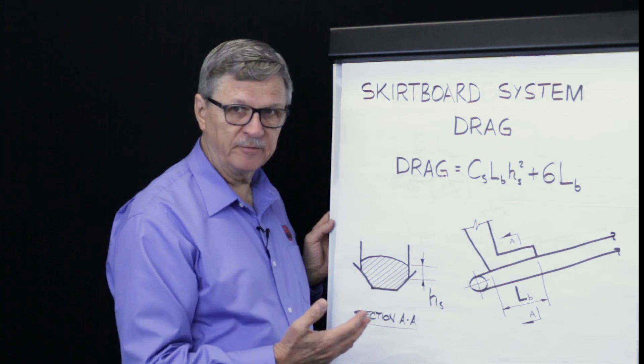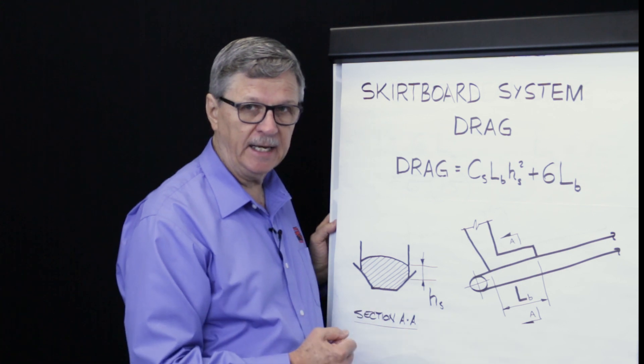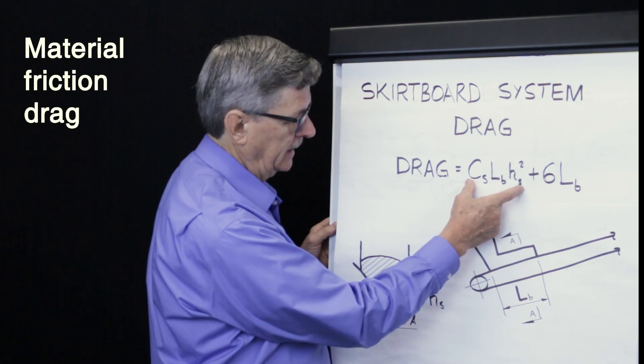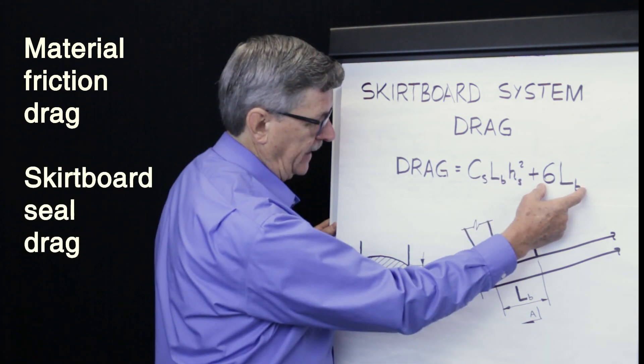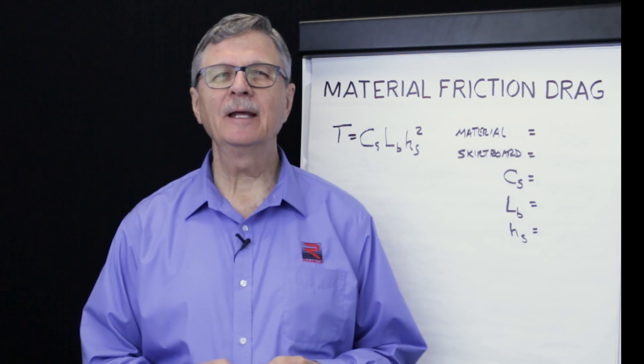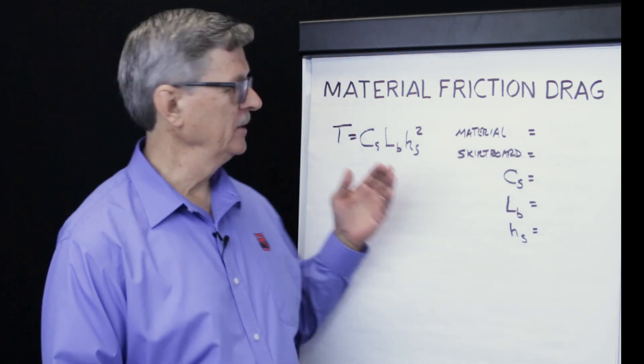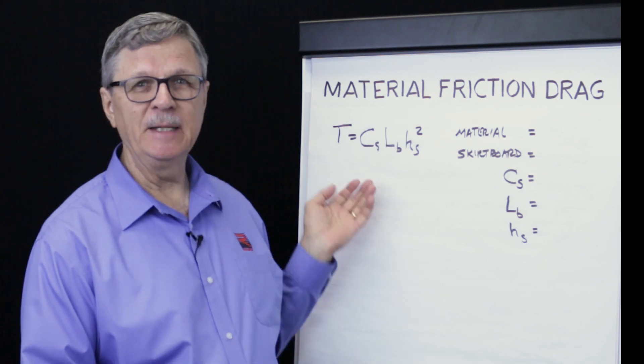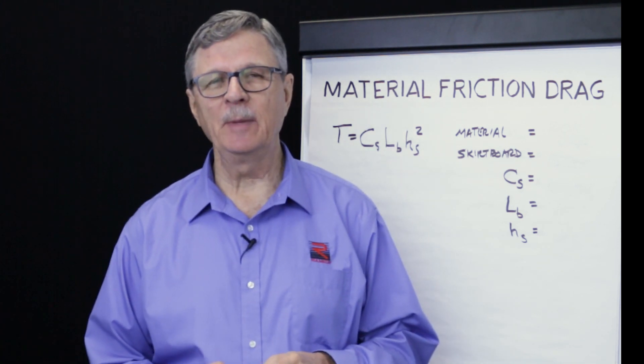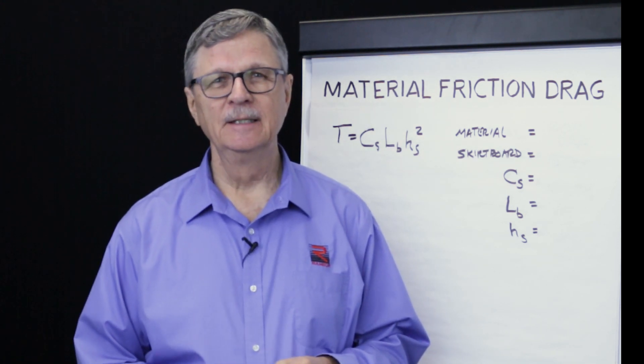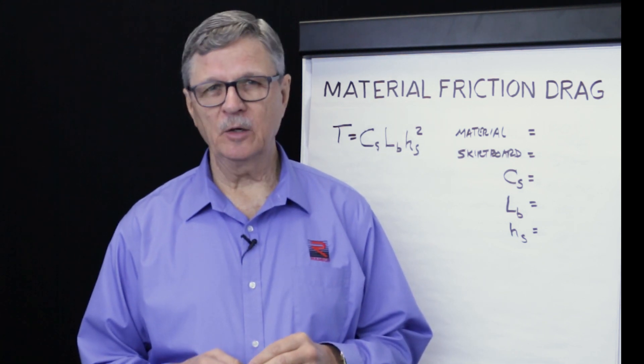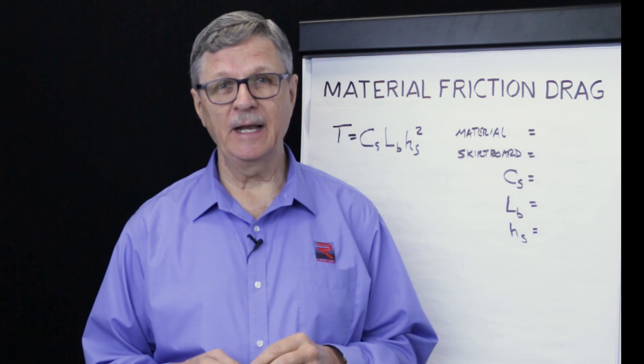The two components of friction that we need to figure out how to calculate are material frictional drag and skirt board seal drag. To calculate material frictional drag within the skirt board system, we can use the equation shown here. This has been developed by the Conveyor Equipment Manufacturers Association, who has also published a list of frictional coefficients which can be used for a variety of materials.